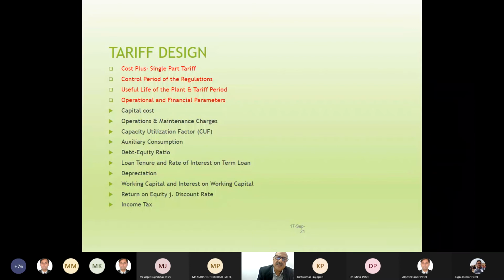Then capacity utilization factor is another important feature for tariff determination. A better capacity utilization factor gives a lower tariff. But with lower capacity utilization, like in solar where it's only around 20%, the whole cost has to be divided over just 20% of the plant's energy, so naturally the cost will be high. In thermal plants, the plant load factor is around 85%, so naturally their generation cost is less.